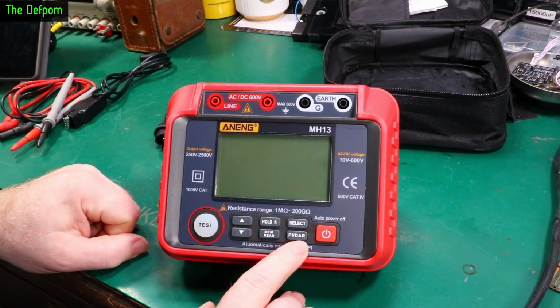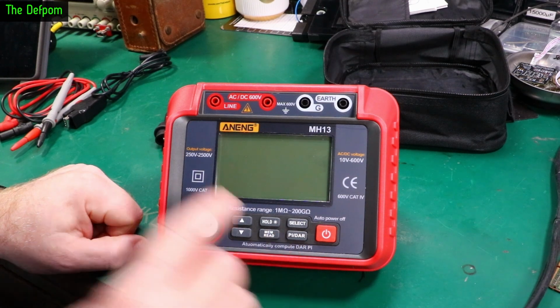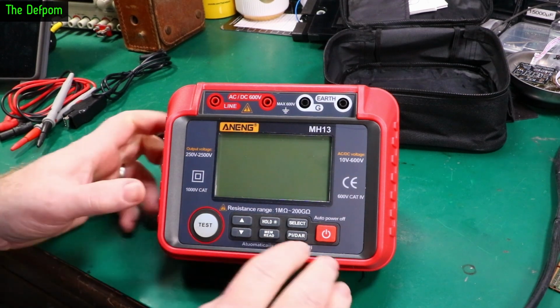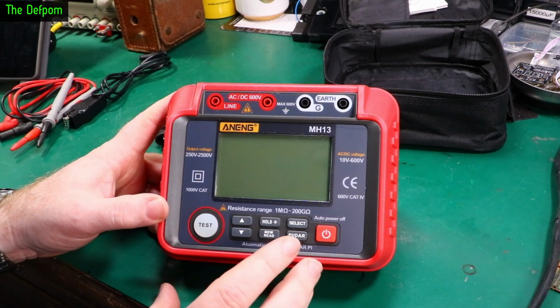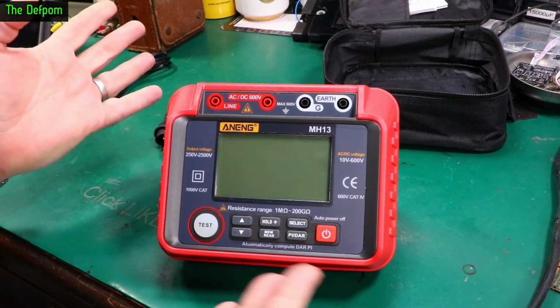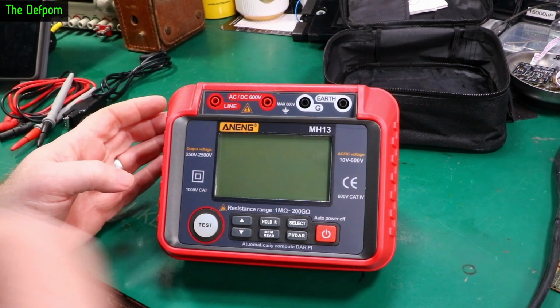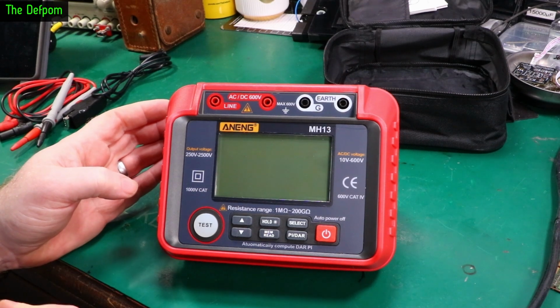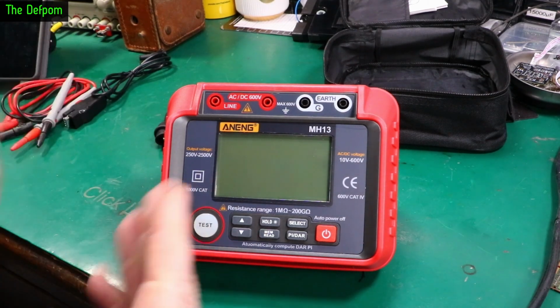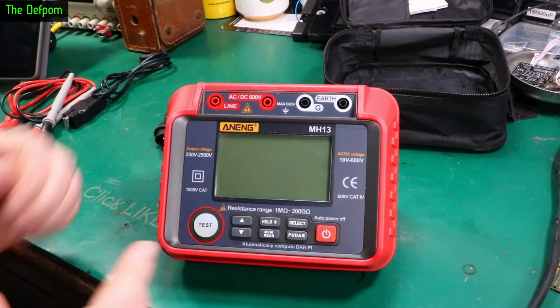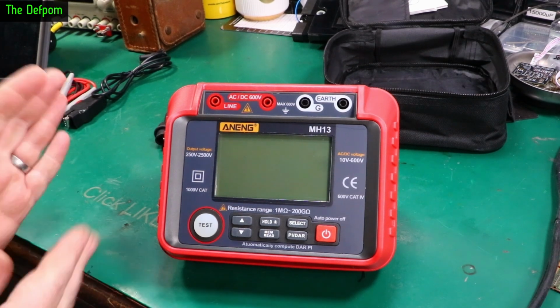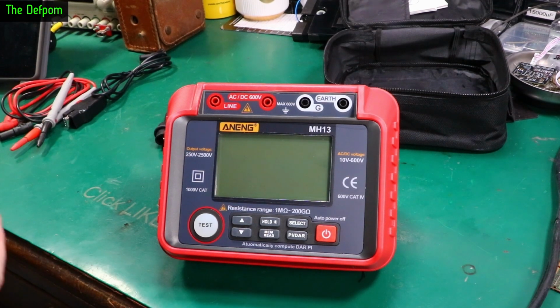DAR is dielectric absorption ratio. PI, I can't remember what that is right now. So what this basically means is you can do a high voltage test for a period of time on a cable or something and see the dielectric absorption of that material, which is actually a measurable specification. So you can actually determine if a material will break down under high voltage over a period of time, rather than just it's okay for 10 seconds - is it still okay after 10 minutes?